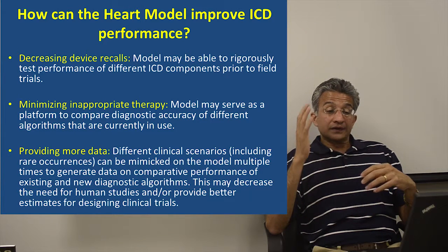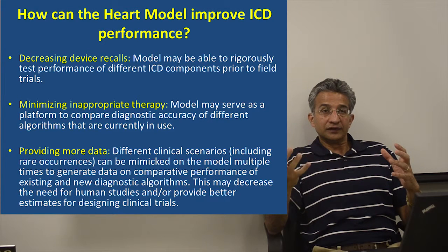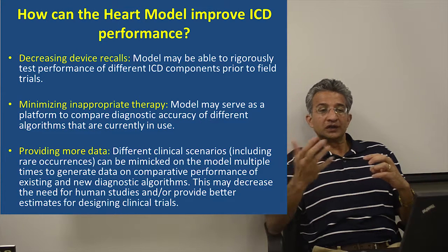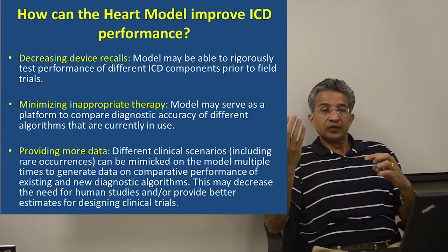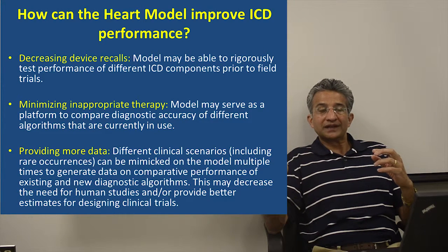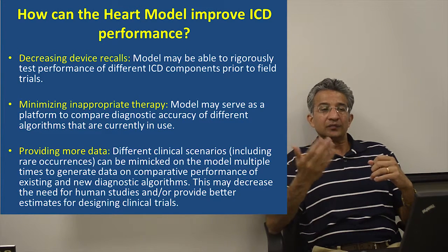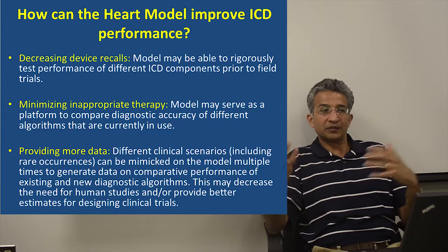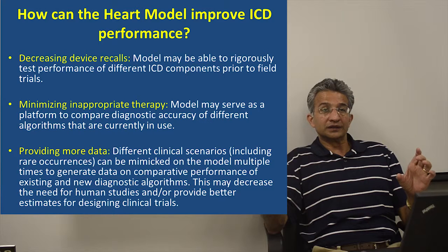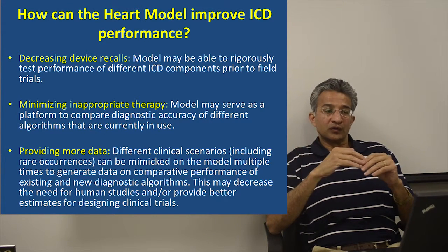And then there are scenarios that are impossible to replicate and predict in the clinical world. They are relatively rare. And so those are the off chance happenings, but in that particular patient who encounters them, so for example, there is a lead breakdown and there is noise, and that noise can cause inappropriate therapy. But that is an almost impossible clinical trial to do because you cannot replicate noise and break down a system in a patient who has had this implanted for life-saving intervention. But the model is one place where you can actually mimic that scenario. So those are the kinds of rare situations which the model can also provide information on.